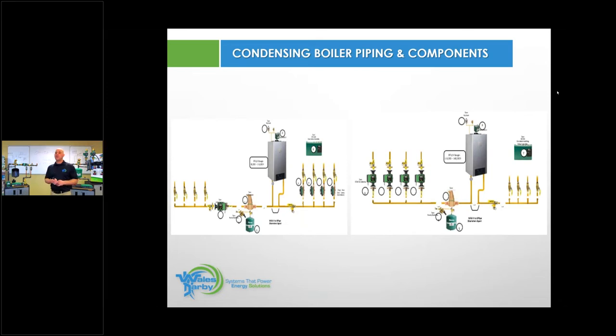And if we were to step over to a condensing version, we would be looking at the same type of components, with the difference being we would need to do primary secondary piping, which is located right here. The rule for primary secondary piping is the maximum distance we want from outside of this T to outside of this T is 4 to 8 pipe diameters of the size of pipe you're working with. So a lot of times you'll see in there it says 12 inch max. Well, if you're with 1.25 inch pipe, that would be 12 inch max. If you're working with larger pipe, it can be a little further. If you're working with smaller pipe, it can be smaller.